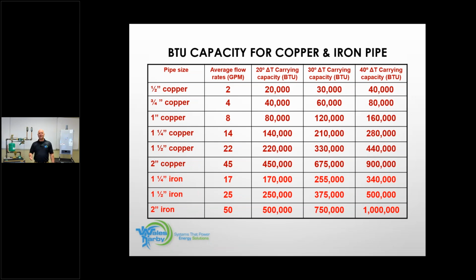I mean, it's not uncommon to see 1-inch pipe carrying 90 or 100,000 BTU. It will just skew your delta T a little bit. And when we talked about feet per second earlier, velocity, it will skew the velocity, and we'll talk about that. So this is a very safe, conservative chart. If you do the install and you adhere to these numbers, you will not be back there for a problem with flow, with noise, with erosion, and you will deliver the BTU that this tells you.